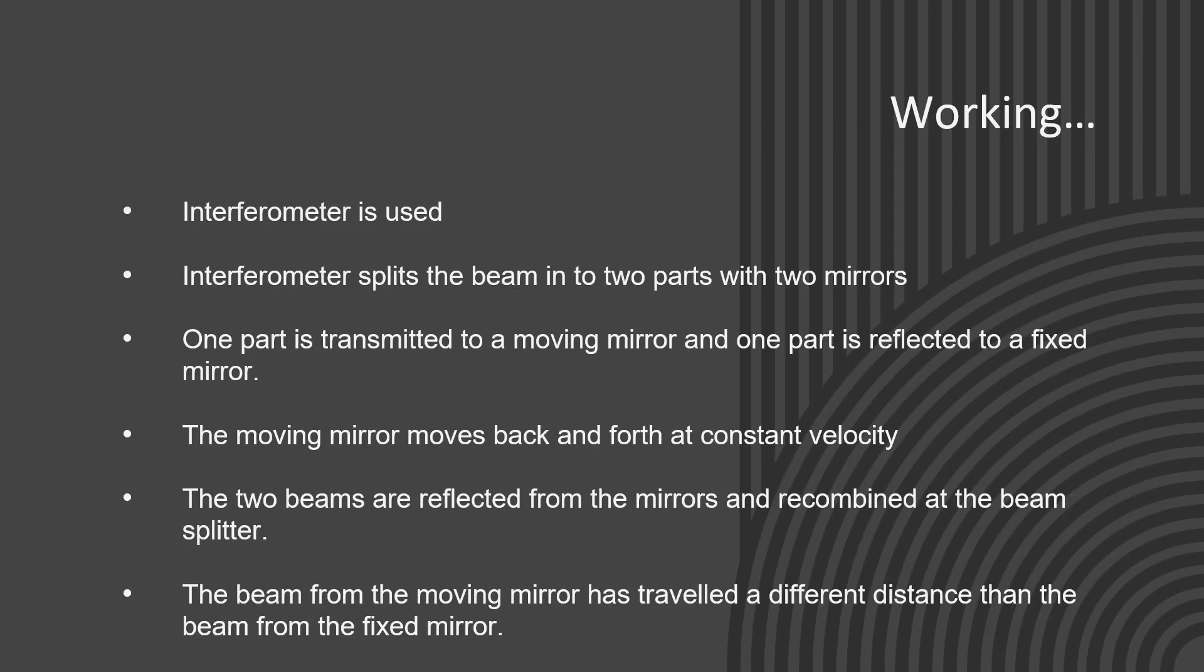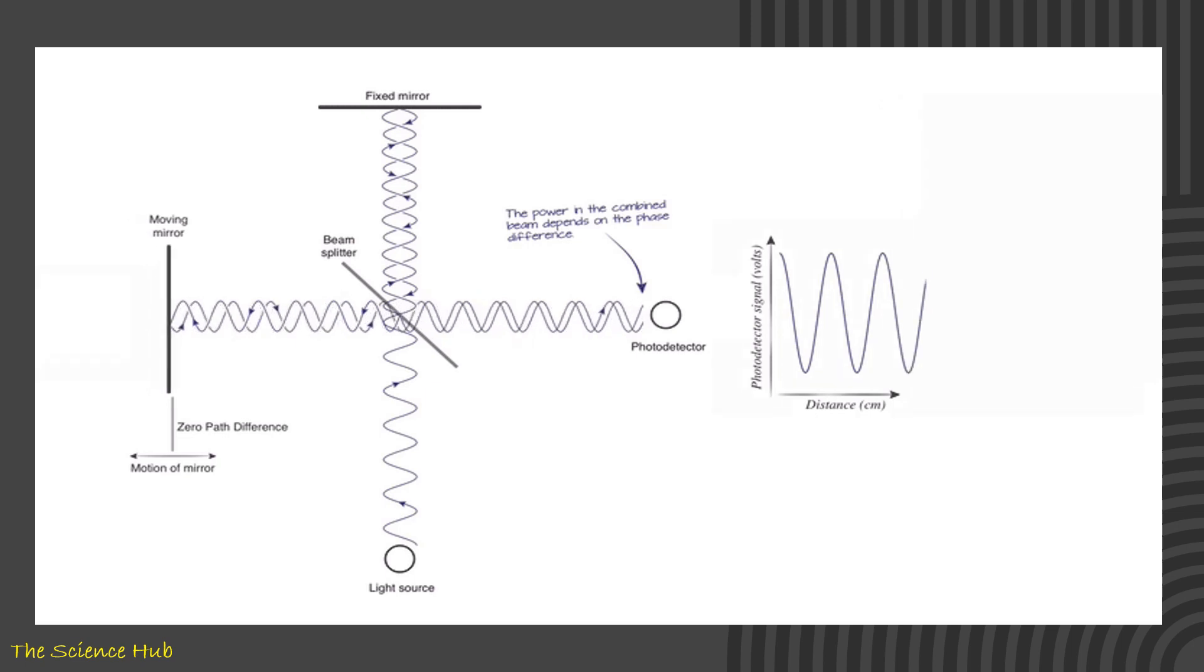Now how FTIR is working: interferometer is used in this spectroscopy. Interferometer splits the beam into two parts with two mirrors. One part is transmitted to a moving mirror and one part is reflected to a fixed mirror. The moving mirror moves back and forth at constant velocity. The two beams are reflected from the mirrors and recombined at the beam splitter. The beam from the moving mirror has traveled a different distance than the beam from fixed mirror. Here you can observe whatever we discussed—how that constructive and destructive phenomena will take place and according to that how data interpretation will take place.